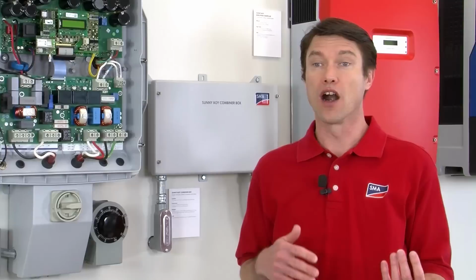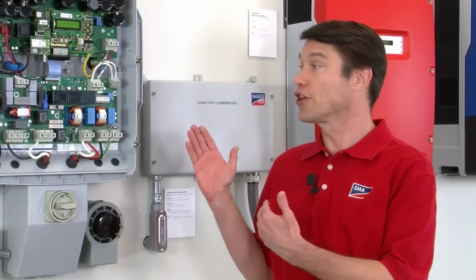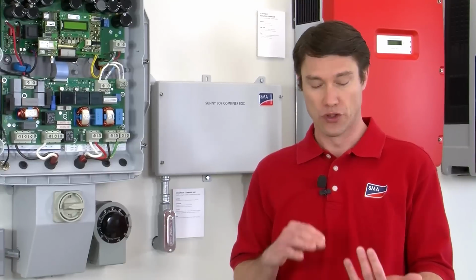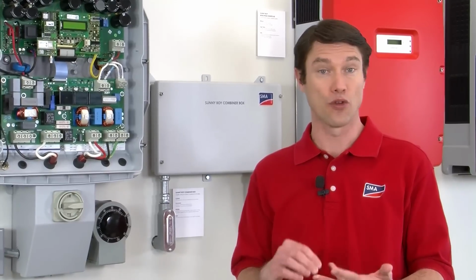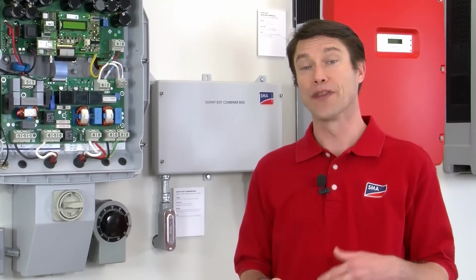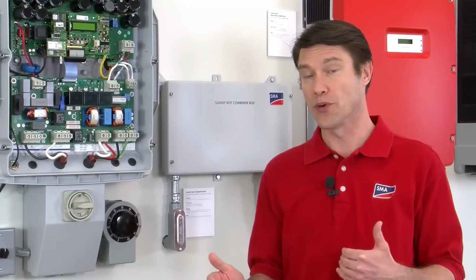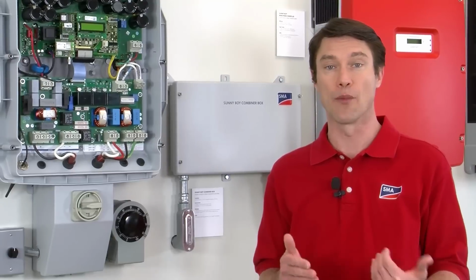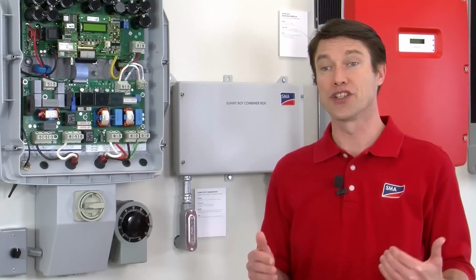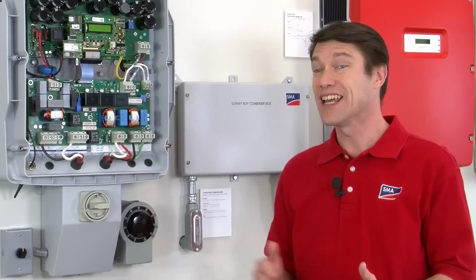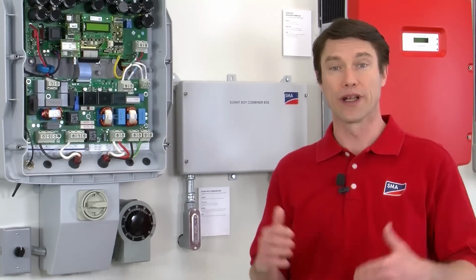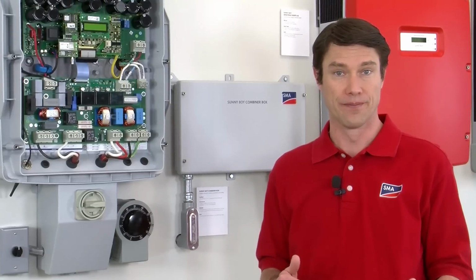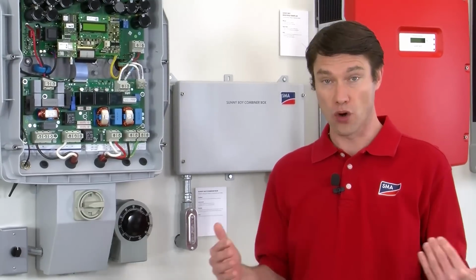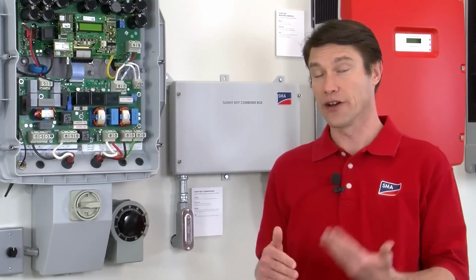to be. Our 5000 to 8000 series Sunny Boy US inverters have multiple VACs that they can work at, 240 volts, 208 volts, or 277 volts. But the plus 10%, minus 12% holds true for whichever one is the nominal value. If that voltage the inverter sees on its terminals here is outside of that range, it will get flagged for the VAC error.